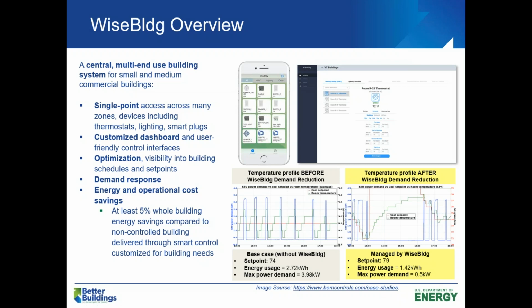The before case showed about 3.98, roughly 4 kilowatts of max power demand. With the optimized new sequence provided by WISE Building, the customer saw only half a kilowatt. So substantial savings if you're able to get all your thermostats and the whole building to communicate correctly, you can get some pretty cool results.